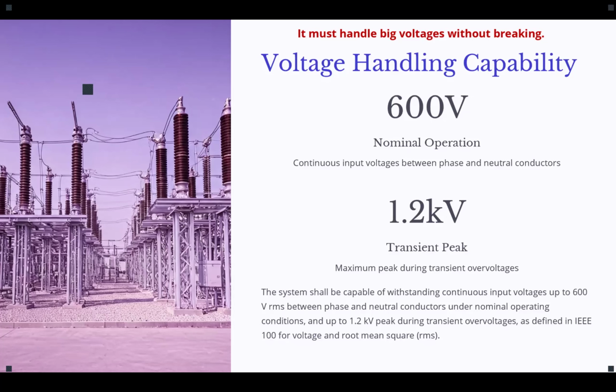We could write: the system shall be capable of withstanding continuous input voltage up to 600 volt RMS between phase and neutral conductor. In what condition? Under nominal conditions. And up to 1.2 kilovolt peak voltage, the first one was RMS, this one is peak, during transient overvoltage, as defined in IEEE 100 for voltage and root mean square. Is that clear? See how different it sounds when you precisely address all the ambiguity.